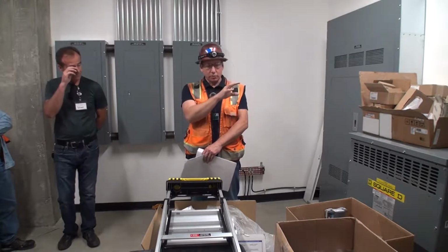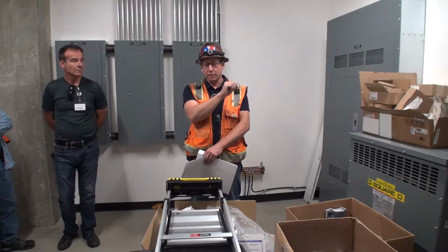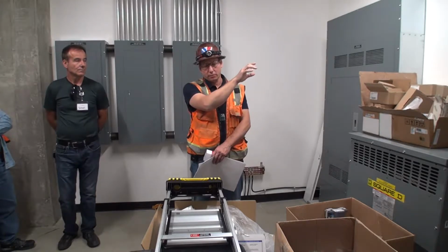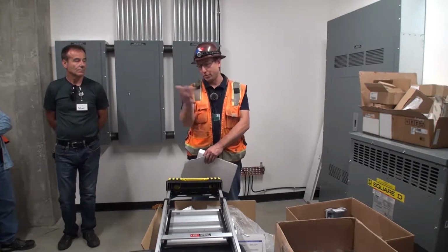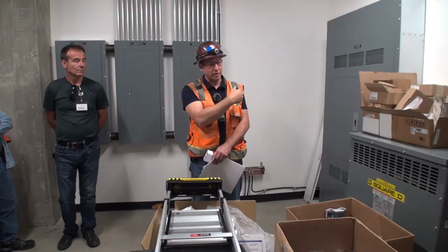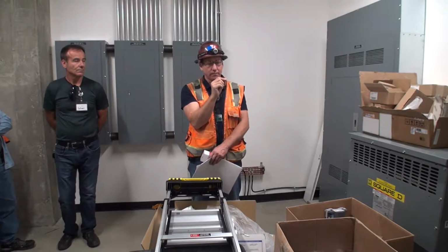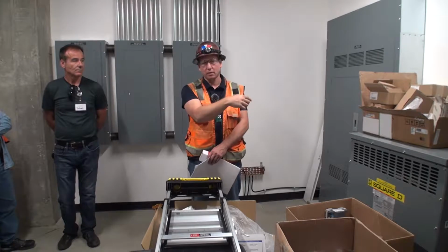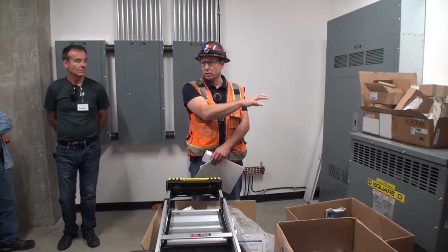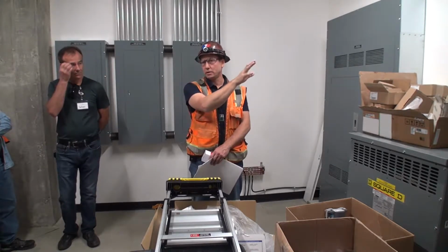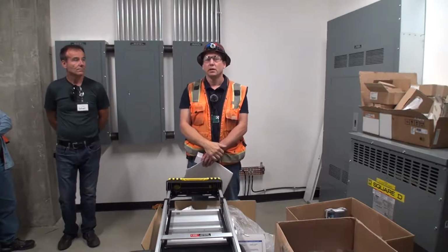So in the main electrical room, we'll take a little look at it, probably explain it a bit better, but we come around the room - literally to the right is one, to the left is the other. One is emergency, one is standby. And so the distribution on the standby comes out at 480 volt, we'll hit a local transformer and then feed the 120 volt panels.